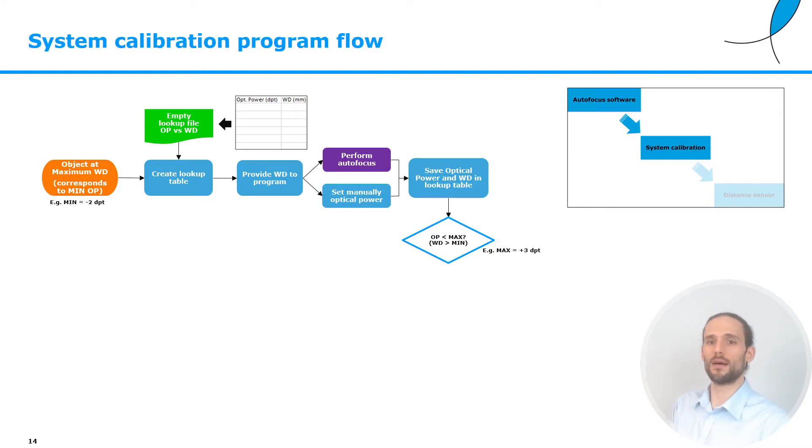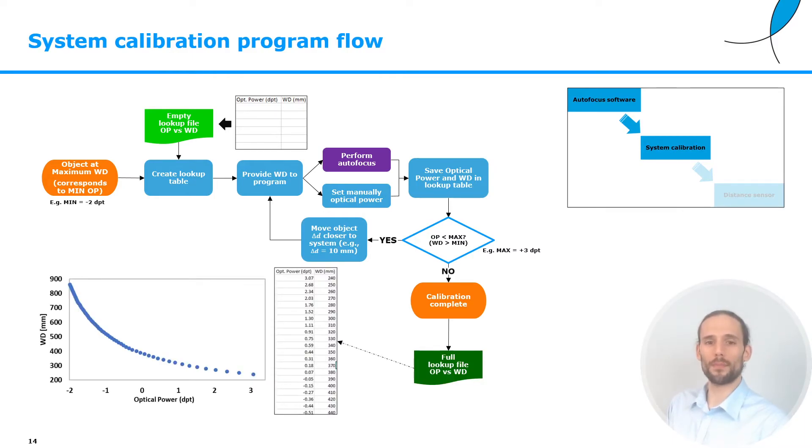If the optical power is still smaller than the maximum optical power, what we will do is basically move the object closer and closer to the system, and we will run again this loop, the calibration loop, until we get to the point where the optical power is bigger than the maximum optical power, or the working distance is smaller than the minimum working distance. At this point, we're done with the calibration, and we will have our lookup table file, which is filled up. For example, for the system I showed you before, this is how the optical power versus working distance looks like. Of course, the more data points one acquires, the more accurate the calibration will be.